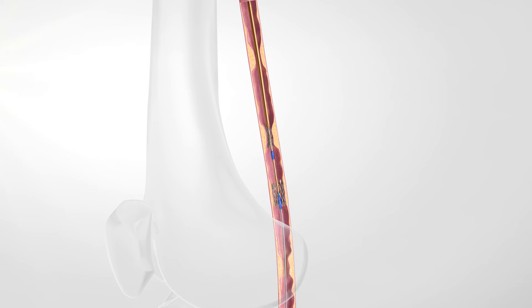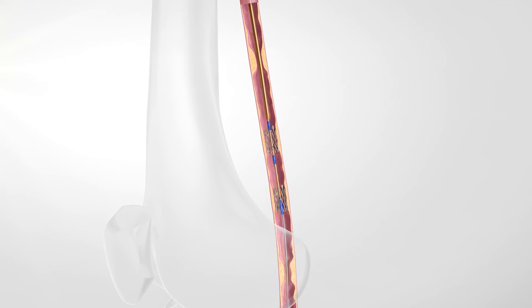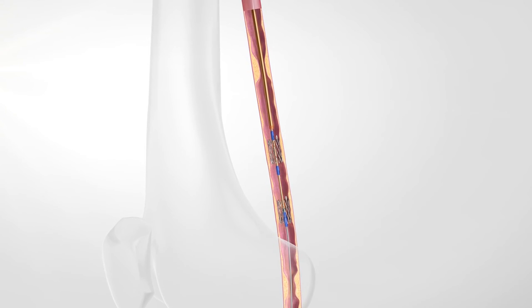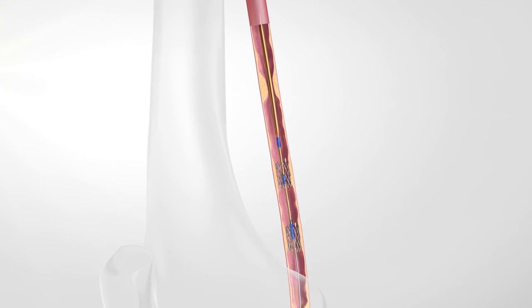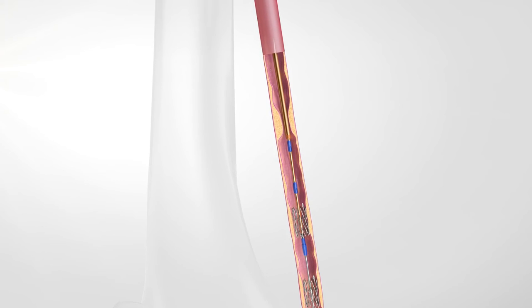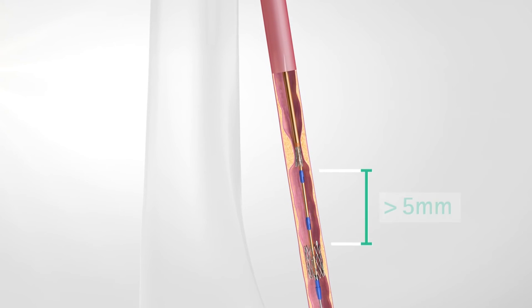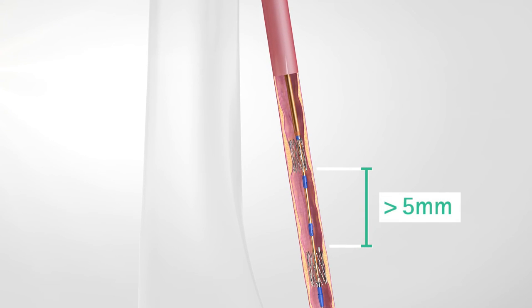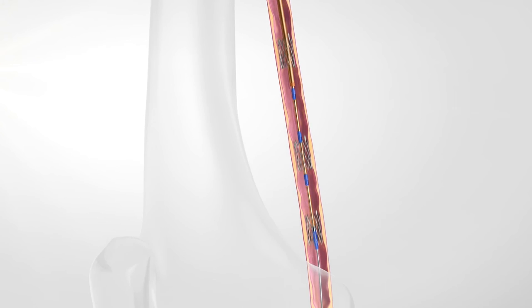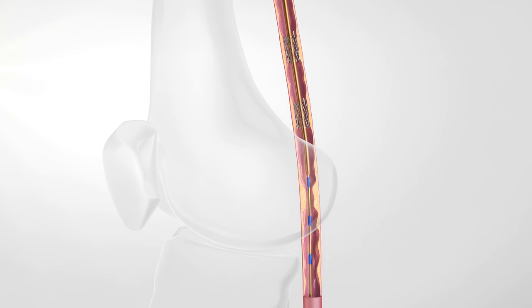Each stent can be implanted only where its scaffolding properties are needed. A distance of at least 5mm between neighbouring stents is recommended. Already implanted stents can be passed to release additional stents distal of the previously treated lesion.